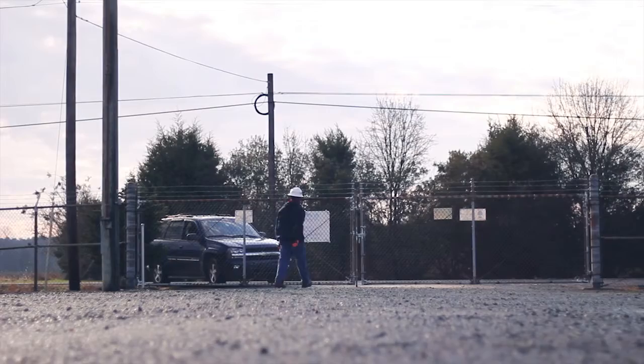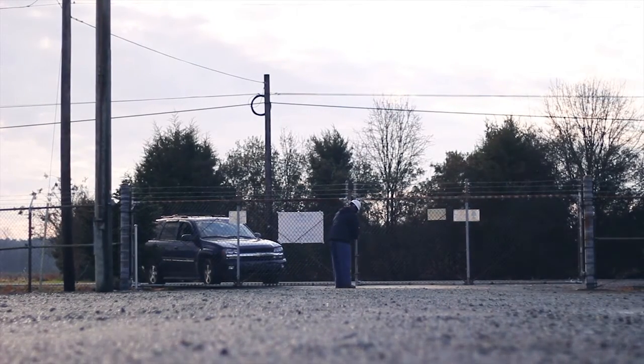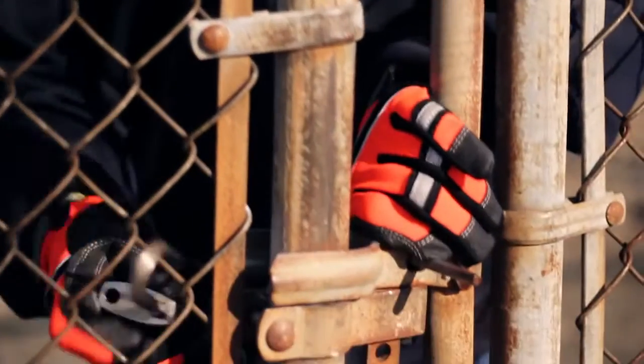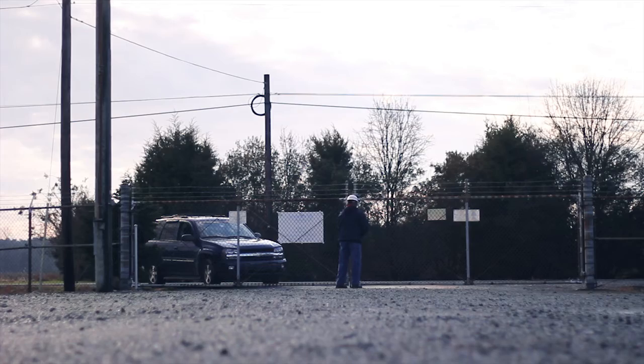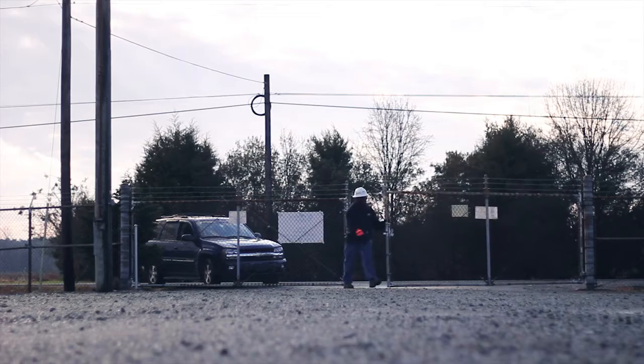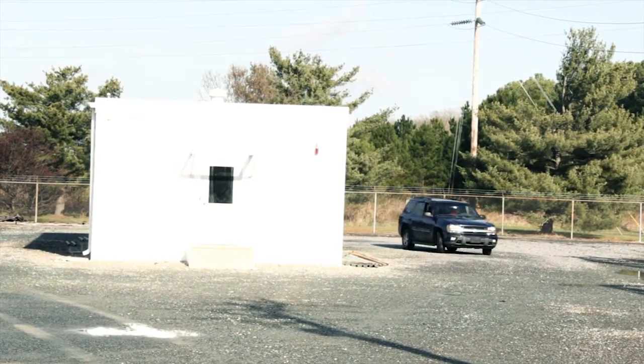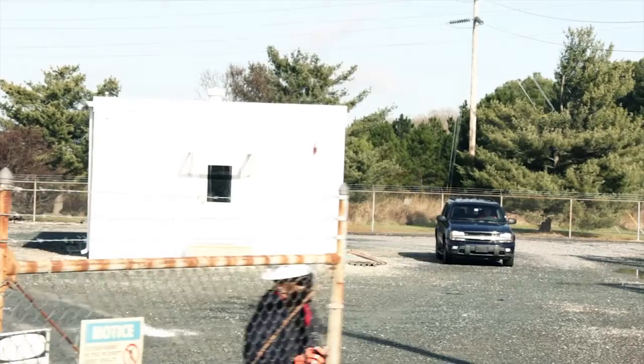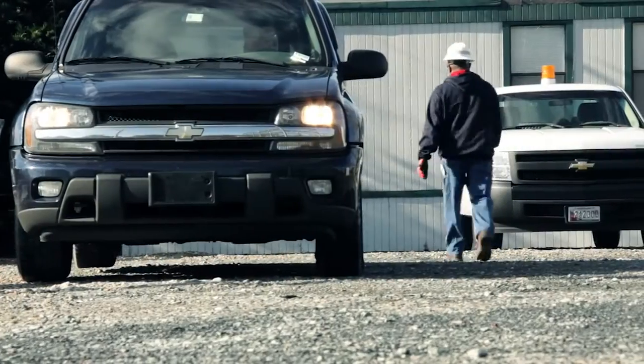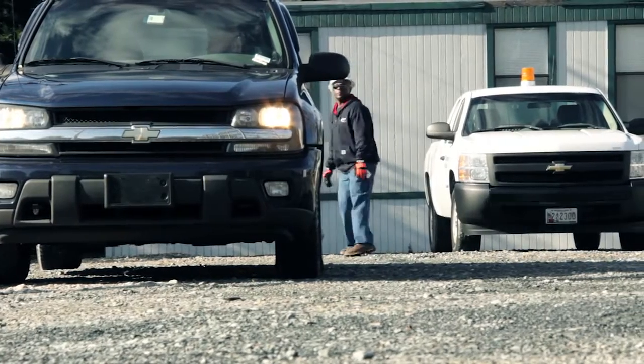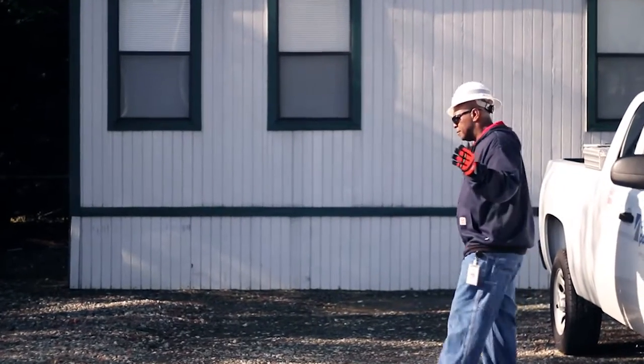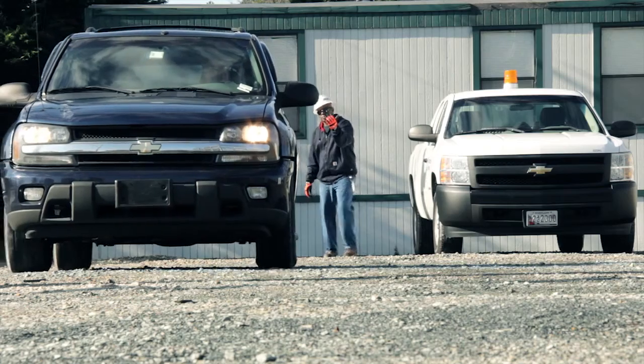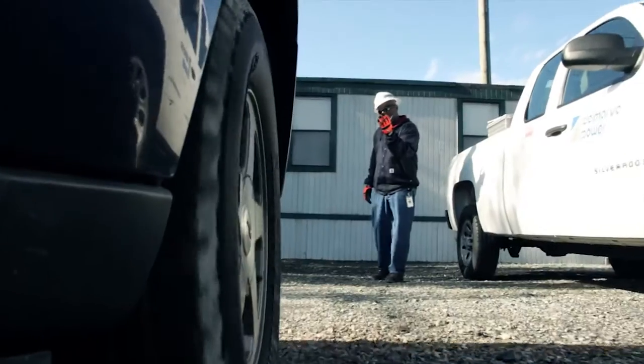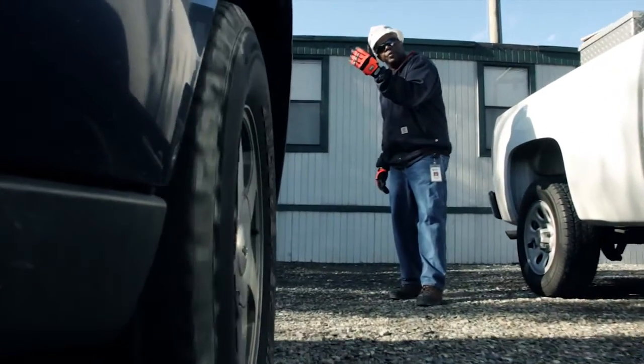As stated in the PHI Safety Manual, perimeter substation doors and gates shall be kept closed and locked when not under the observation or control of an attendant. All attendants must be within close proximity to open gates to maintain proper control of the gate. When it comes to parking your vehicle, you must pull through in all parking spaces to avoid having to back out to leave. If you are unable to pull through, backing your vehicle into a parking space is preferred. If a second person is available, that person must act as a guide when backing the vehicle into or out of a space. Every effort should be made to park your vehicle as far away from exposed energized equipment as possible.